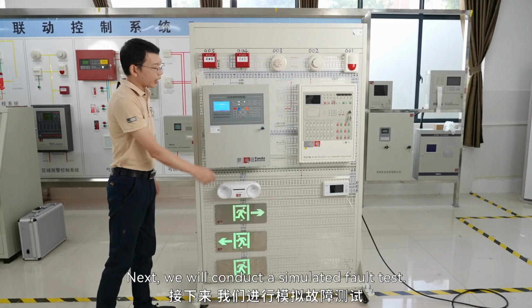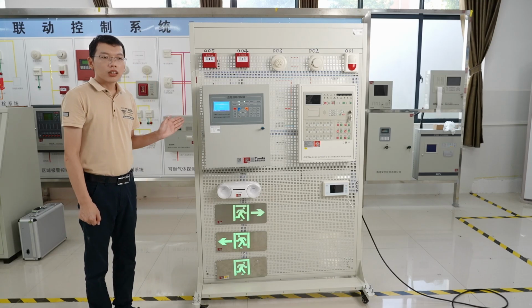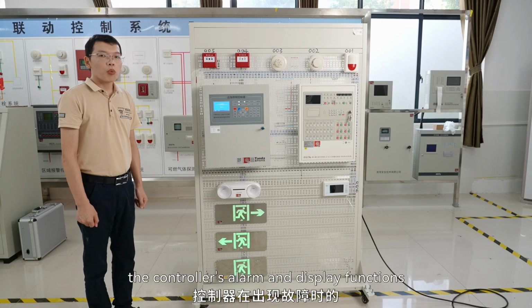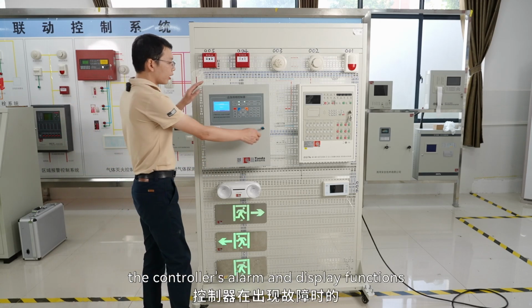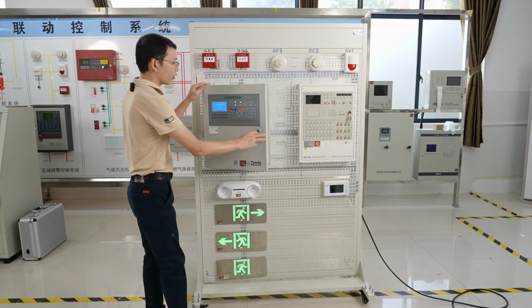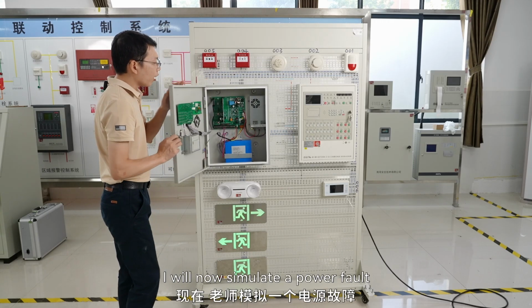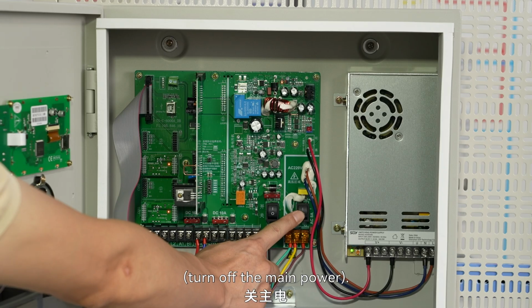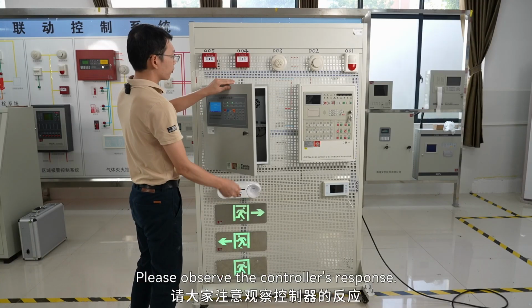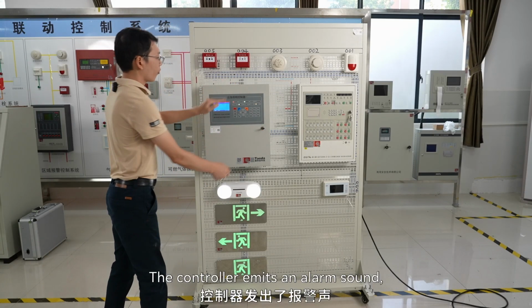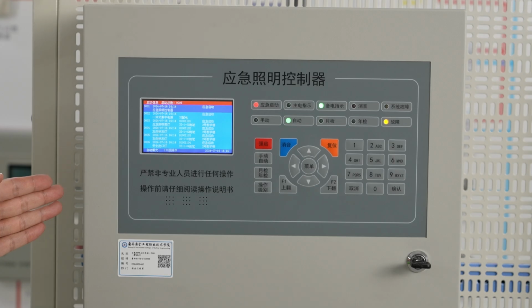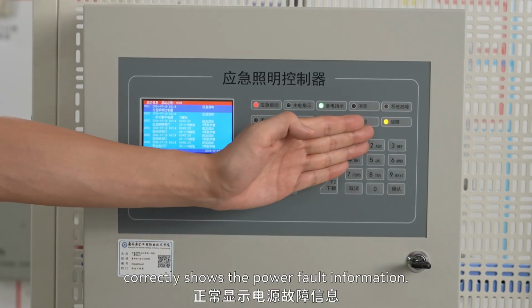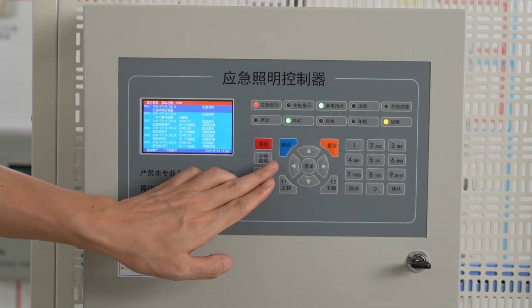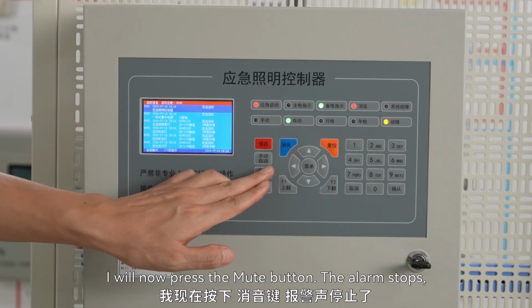Next, we will conduct a simulated fault test. This test aims to verify the controller's alarm and display functions during a fault. I will now simulate a power fault. Turn off the main power. Please observe the controller's response. The controller emits an alarm sound, and the display screen correctly shows the power fault information. I will now press the mute button.